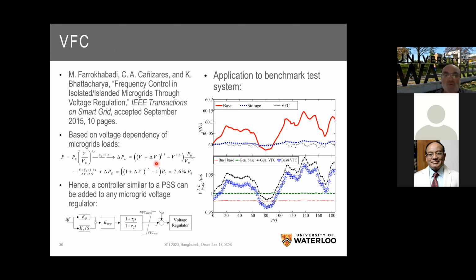So through regulation of the voltage in the grid, you can basically take advantage of it to regulate frequency. You introduce a frequency control loop, similar to a PSS, which regulates the voltage of your voltage sources in the system, which can be diesel generators or batteries as well. Here you can see the result of wind variations and how the frequency changes in the system.